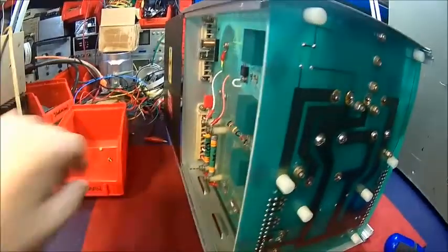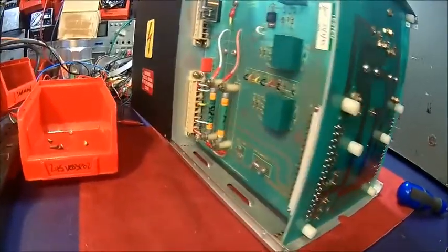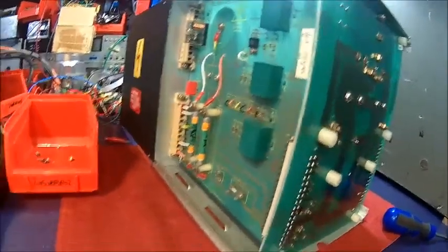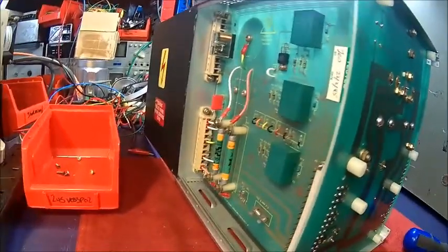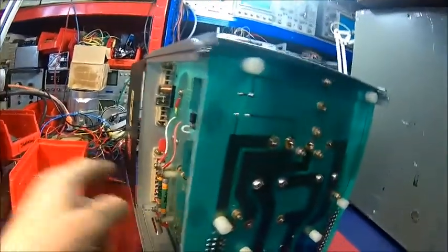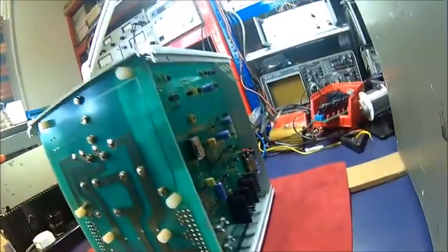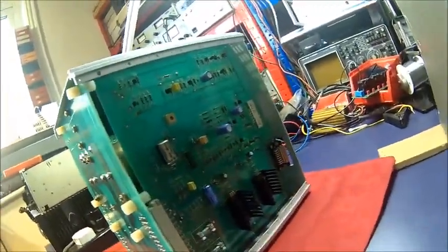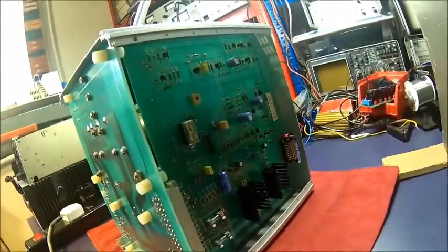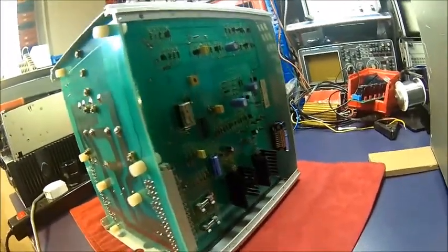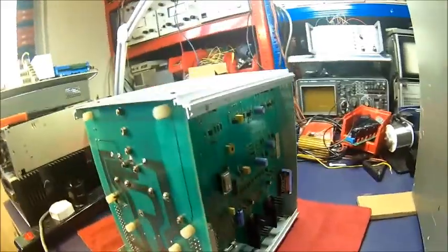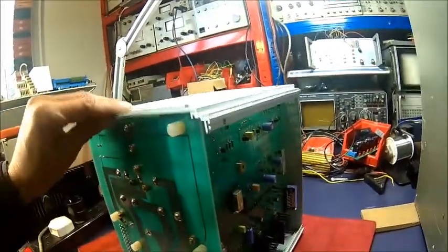So what we're checking for, that's the reason why we take it completely apart, is just burnt components, because these sometimes have issues. These are high-speed fuses here, and they look good - nothing burnt over here. Check the fuses if they're good, but everything looks pretty good actually, so we should be fine.